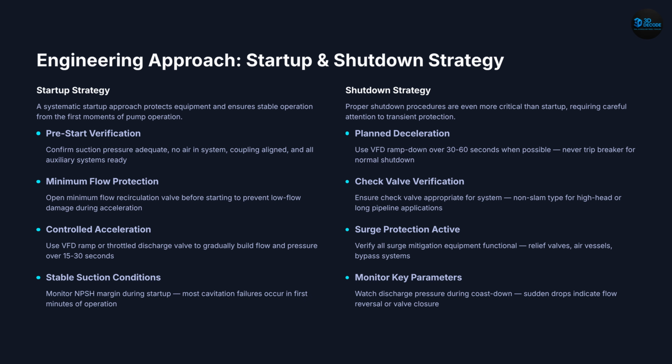Slide 11. Engineering strategy. A proper strategy includes safe startup and controlled shutdown. Use VFD ramp up and ramp down. Ensure minimum flow protection. Verify check valve performance. Monitor pressure during transitions. This approach prevents failures.